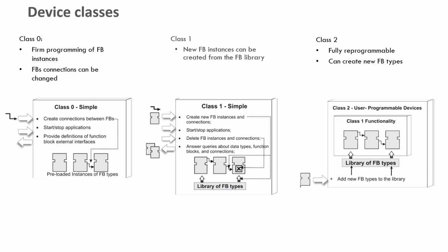So device class 1 can create new function block instances from the library that is stored in the device, but it cannot change this library during its lifetime. So engineering tool cannot send new function block types to update this library.